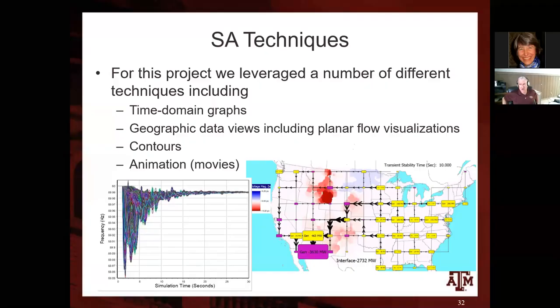Sometimes when you have these large transfers, you do get voltage magnitude drops, and that was a concern in the synthetic grid, and it was a concern in the actual grid. We talked with the utilities involved and discussed the particulars of what we were seeing in the actual system, and they did not think it was unusual. The good thing about local voltage issues like this is they usually can be fixed without too many issues. But in this particular synthetic grid, we were getting some major voltage problems in Wyoming.